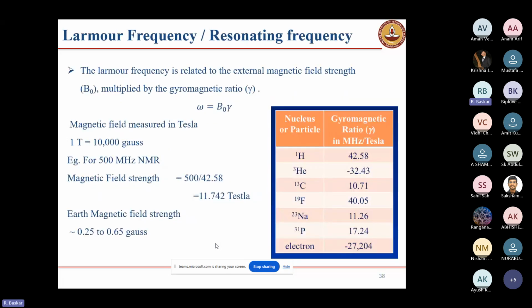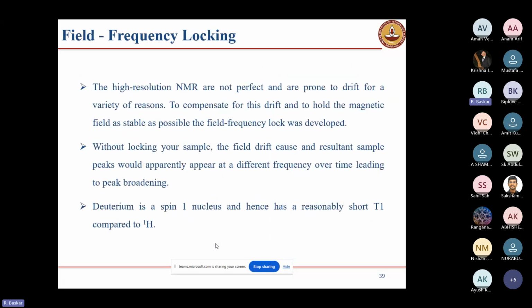Once wobbling is over, then we have to do the field locking. The locking will improve the spectral resolution and reduce the line broadening, leading to sharper signals, and we will get a well-resolved spectrum. The locking will also enhance the reproducibility. If we are doing a longer experiment, we will get a stable spectrum. Field lock is essential for high-quality NMR data.